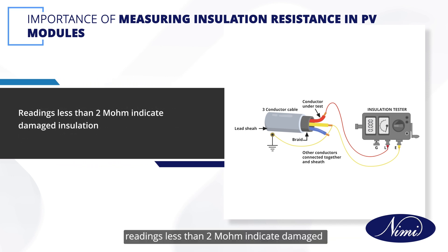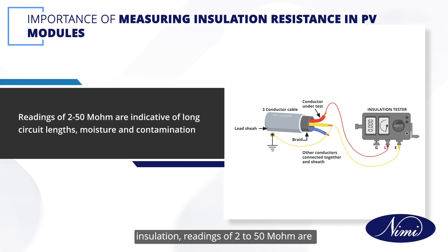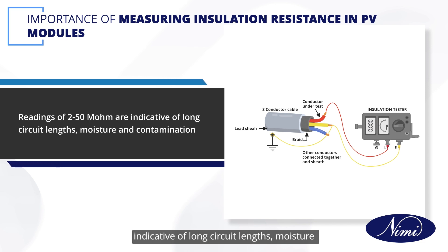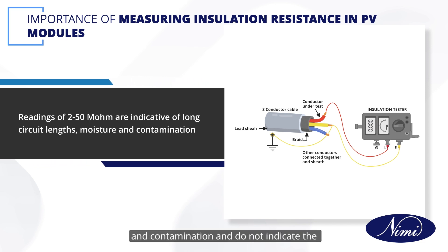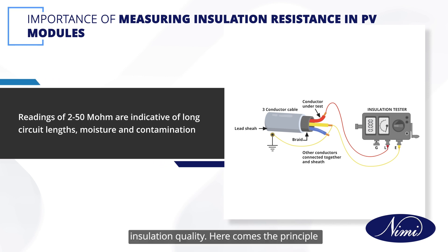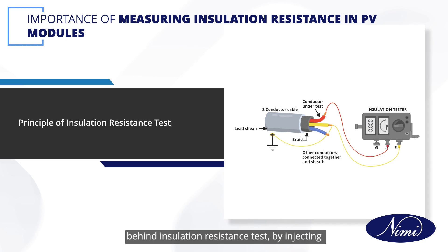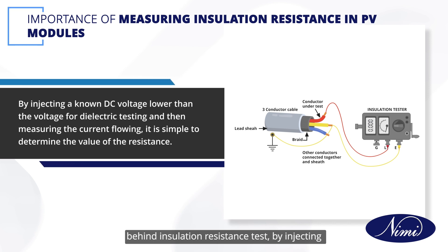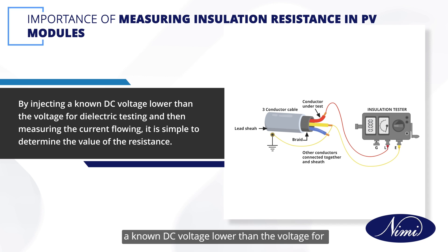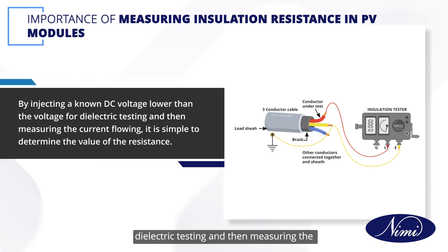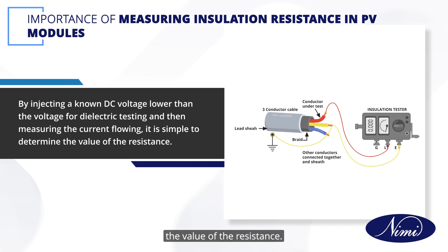Readings less than 2 megohm indicate damaged insulation. Readings of 2 to 50 megohm are indicative of long circuit lengths, moisture and contamination, and do not indicate the insulation quality. The principle behind insulation resistance testing is: by injecting a known DC voltage lower than the voltage for dielectric testing and then measuring the current flowing, it is simple to determine the value of the resistance.